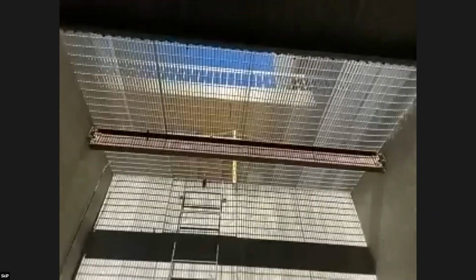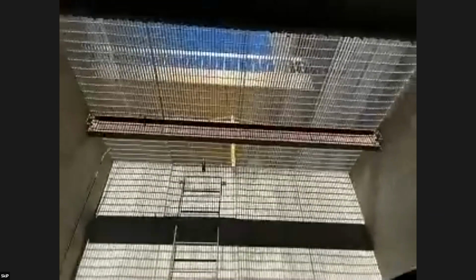So now, where are you now? We need to bring fresh air in. Even though these air handlers are down in the basement, before COVID the rule of thumb was 15% fresh air. We would circulate the air, but always bring in at least another 15% fresh air. If we didn't, CO2 levels would go up and you'd all fall asleep in class, and it would be my fault instead of yours for staying up too late. Now with COVID, we're trying to bring in as much outside air as possible, anywhere from 50 to 100%, depending on the weather and how we can keep up. That way we bring in more fresh air.